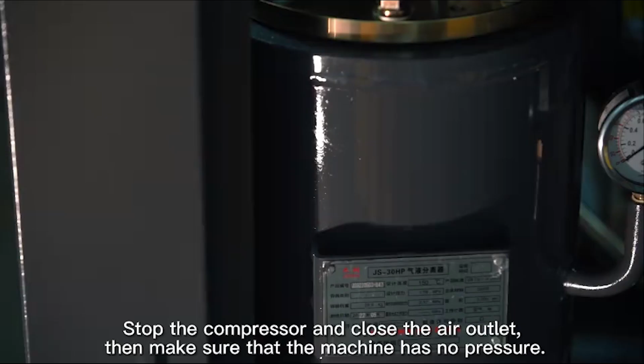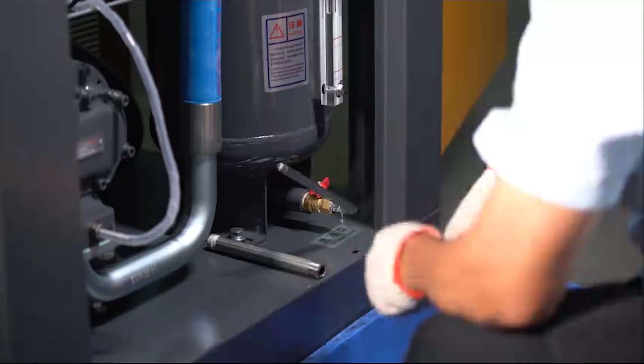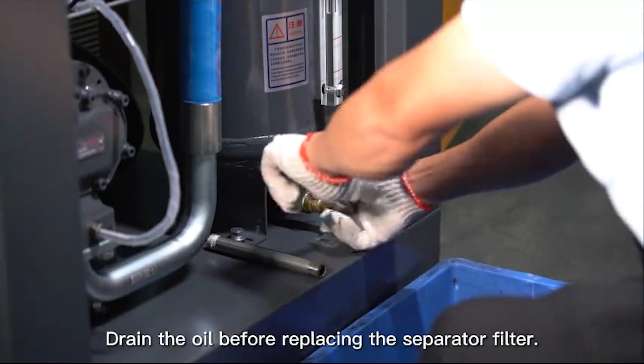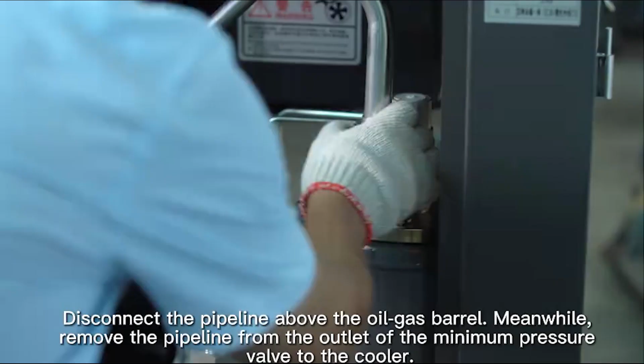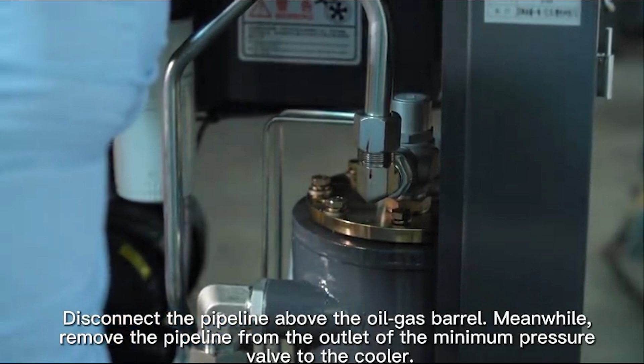Stop the compressor and close the air outlet. Then make sure that the machine has no pressure. Drain the oil before replacing the separator filter. Disconnect the pipeline above the oil gas barrel. Meanwhile, remove the pipeline from the outlet of the minimum pressure valve to the cooler.